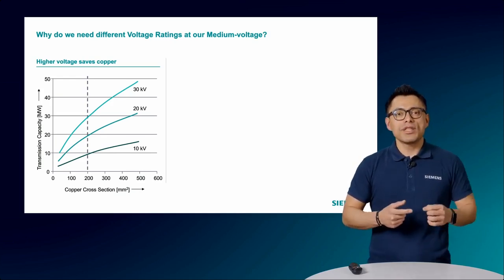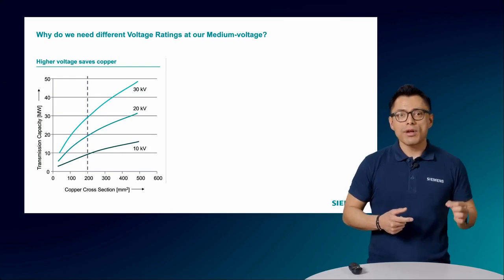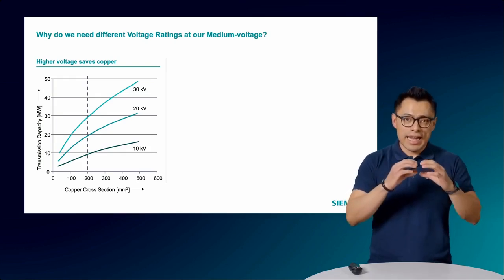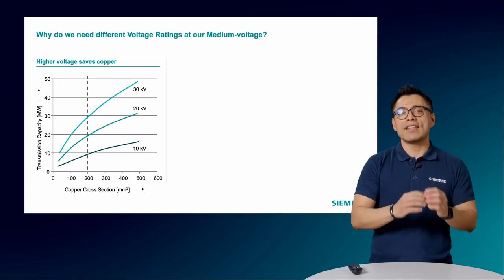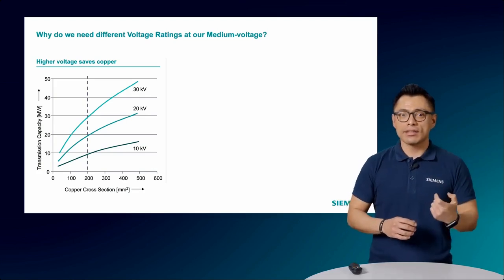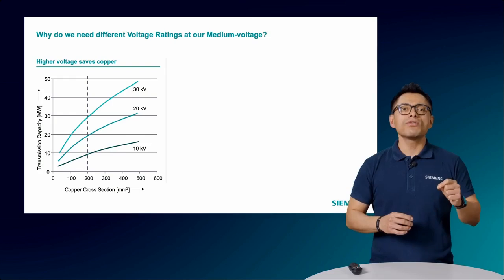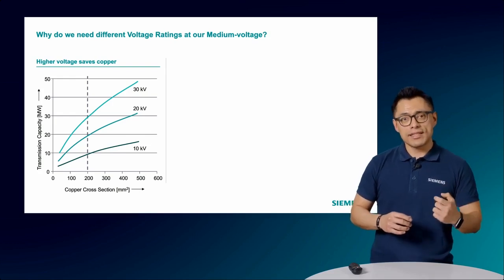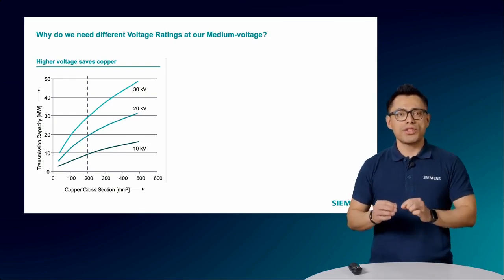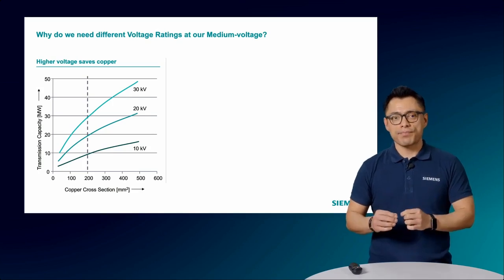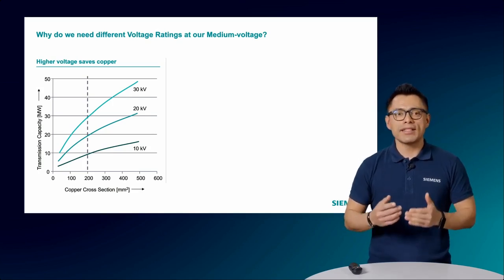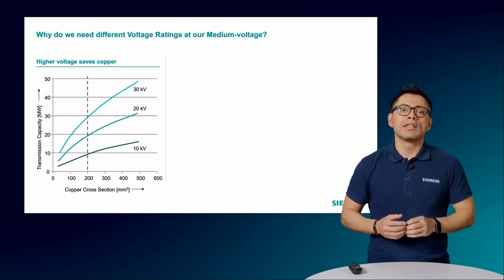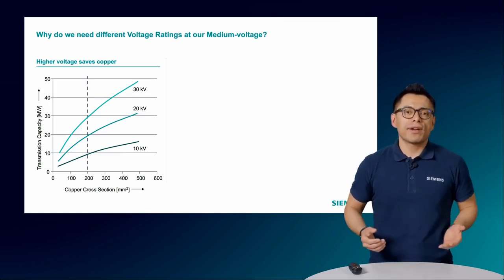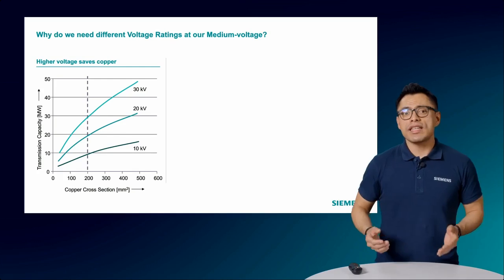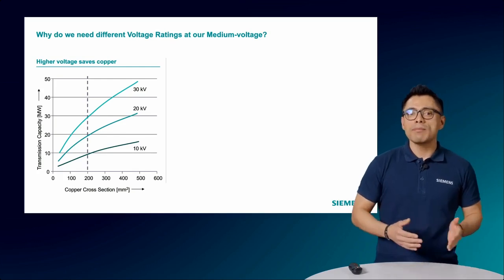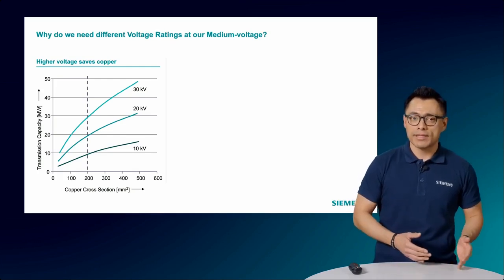Higher voltage reduces the current. Lower current means a reduction in the cable cross-section, which has a direct impact on the cable cost. Low current also reduces the losses due to cable resistance. This makes the power transmission more efficient over distances. Another reason is optimizing equipment size and cost. Different applications require different voltage ratings. By using the appropriate voltage rating, we can optimize the size and cost of the equipment.